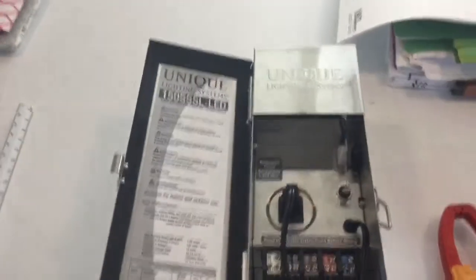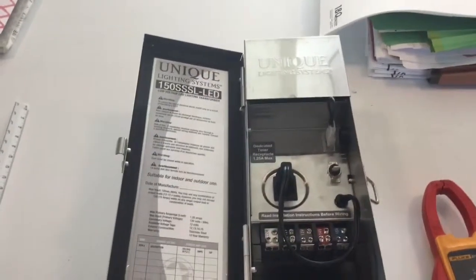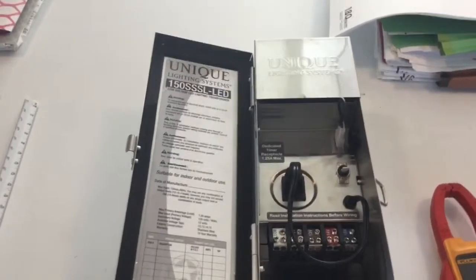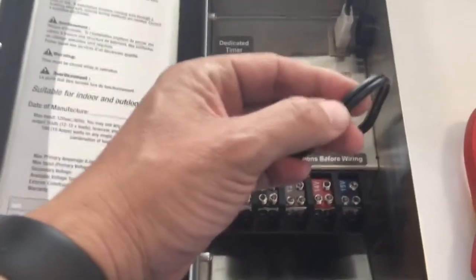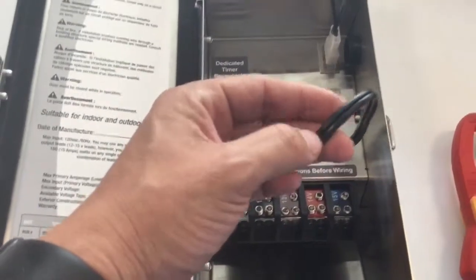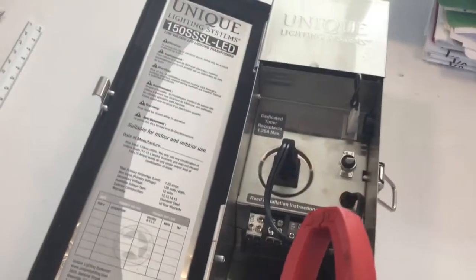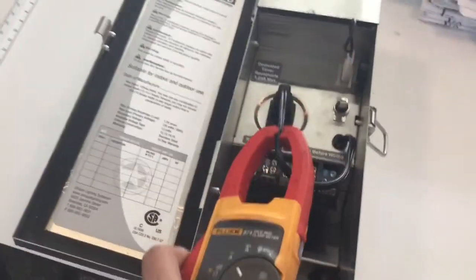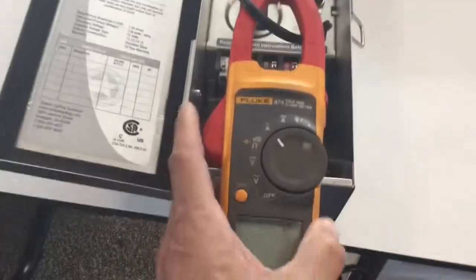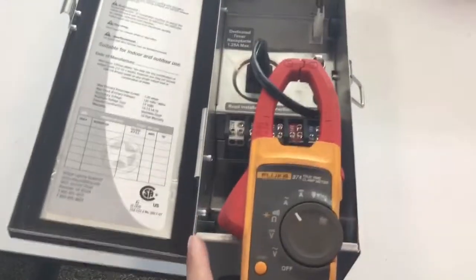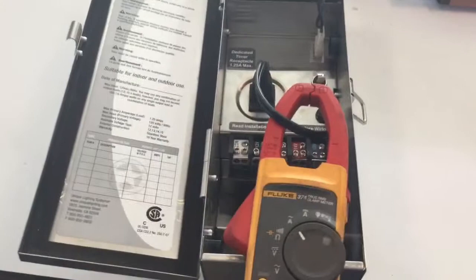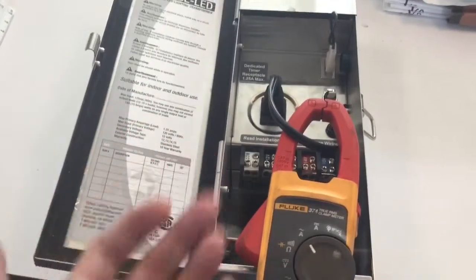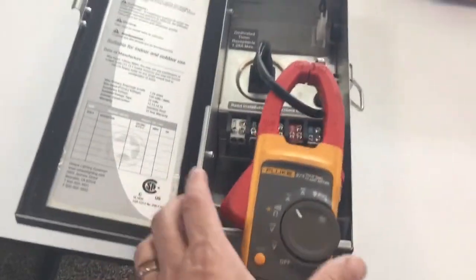If by chance you're using a Unique Lighting transformer that, let's say, is a 360 or higher, what we've done on those transformers is we've actually taken the cord that's here. You can see that there's two together. On the bigger transformers, this cord would be separated. That gives you the ability to take your amp probe and just grab one of those wires. If you were to come in here and actually grab both wires like this and go around it, you'd get a 0 reading, because basically it's alternating current and both these wires are canceling each other out. So you need to circle around just one of them in order to get a reading.